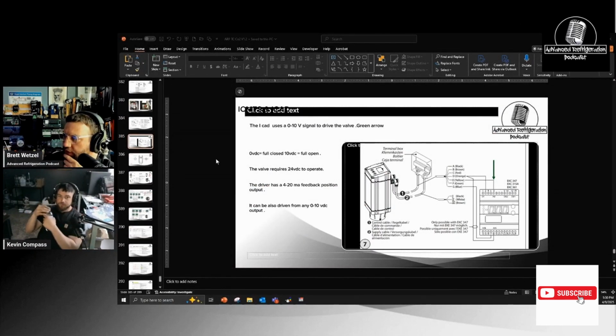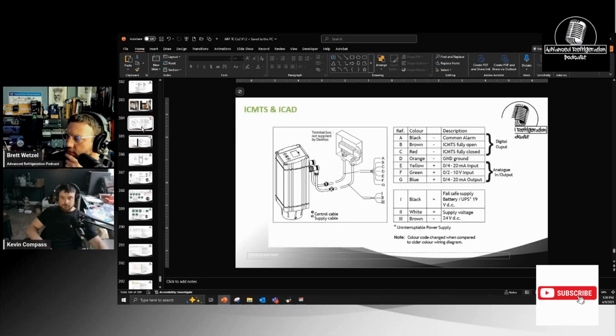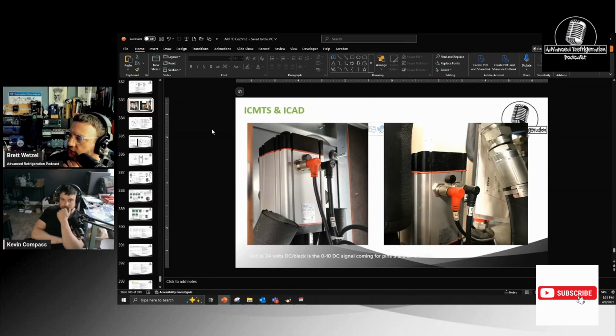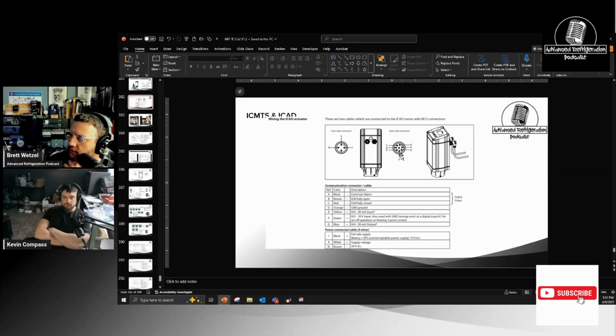So I'm going to just add this to here real quick, just to solidify what you were talking about. Right here, here's all your terminals for this thing, right? So you have common alarm, fully open, the digital output. You're talking about the analog in, so you can go 10 volts, 4 to 20, and then 4 to 20 input, 4 to 20 output, and then basically 10 volt output. And so these are basically those terminals is what you were talking about right here. So if you flip those guys around, those pins are really itty bitty teeny tiny. So that's what he was talking about when he was making fun of my meter leads.